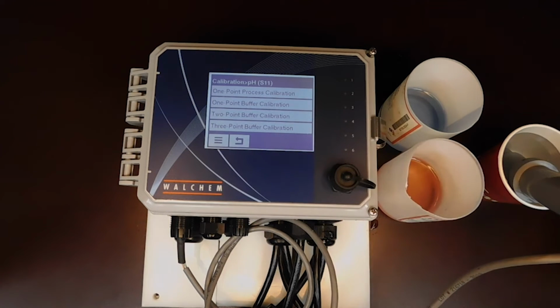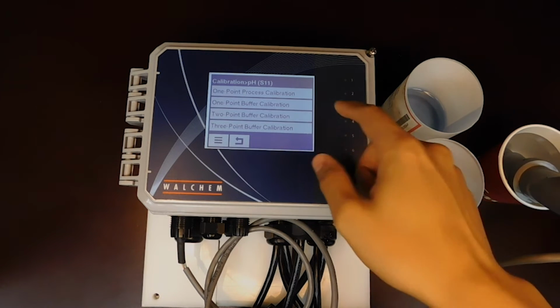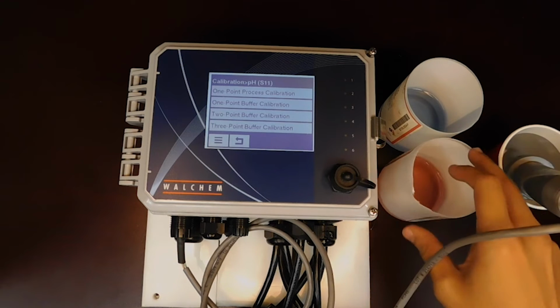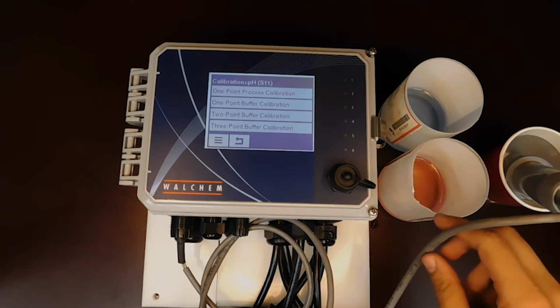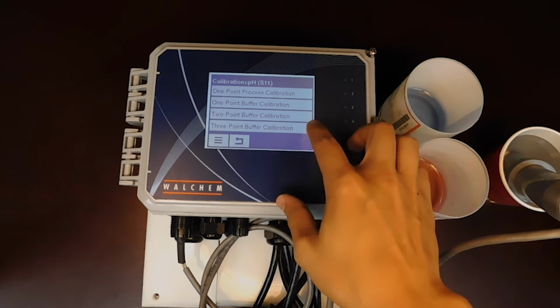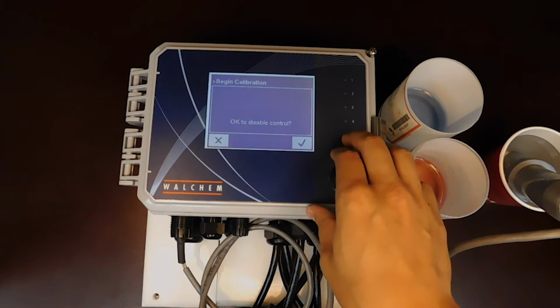The first is one-point process. That's where you don't take the pH probe out of the process and you measure the pH with a separate meter and enter the number. A one-point buffer calibration is where you only use one buffer as opposed to the two we're going to use today. We're going to be using a two calibration buffer today.